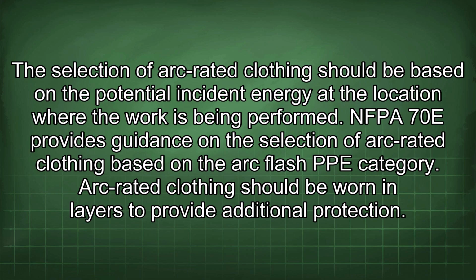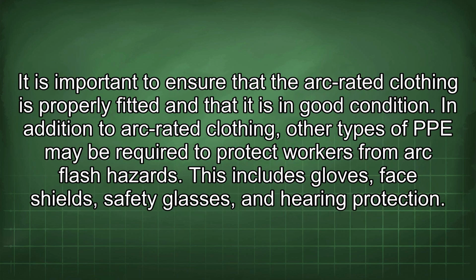NFPA 70E provides guidance on the selection of arc-rated clothing based on the arc flash PPE category. Arc-rated clothing should be worn in layers to provide additional protection. It is important to ensure that the arc-rated clothing is properly fitted and that it is in good condition.